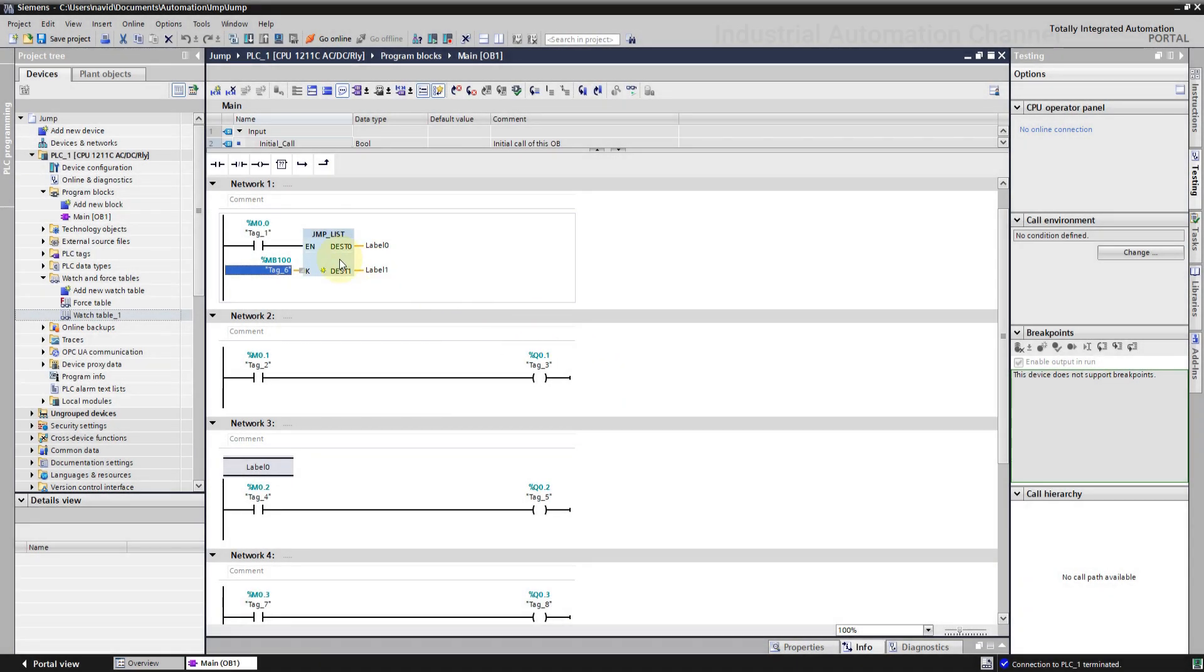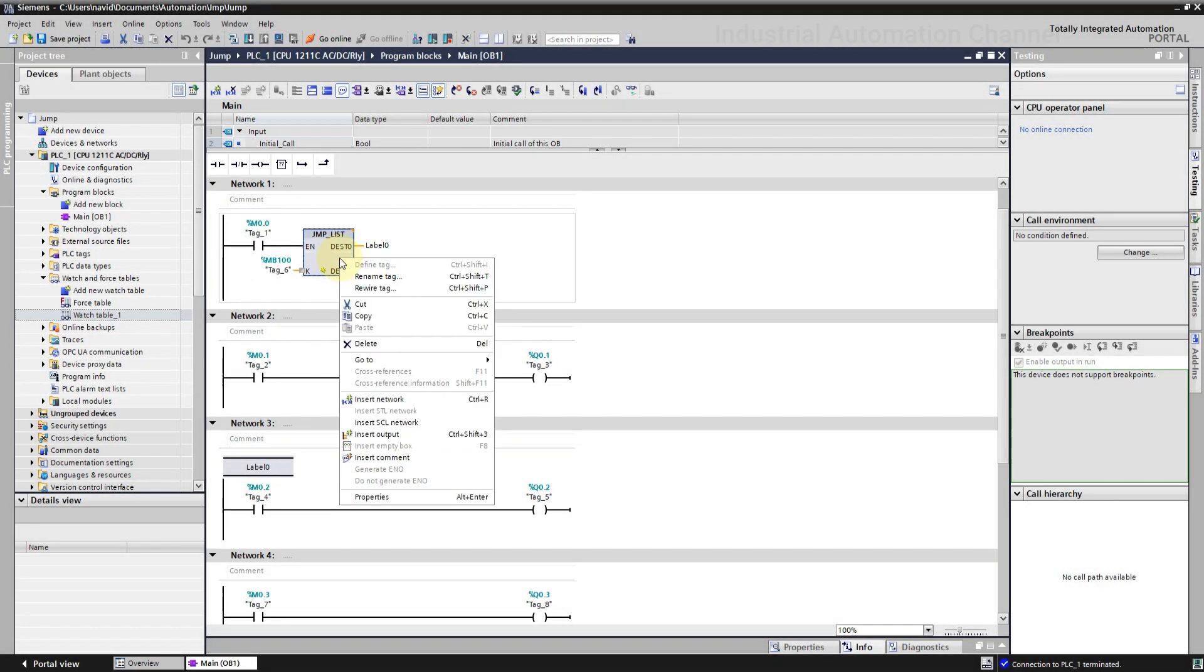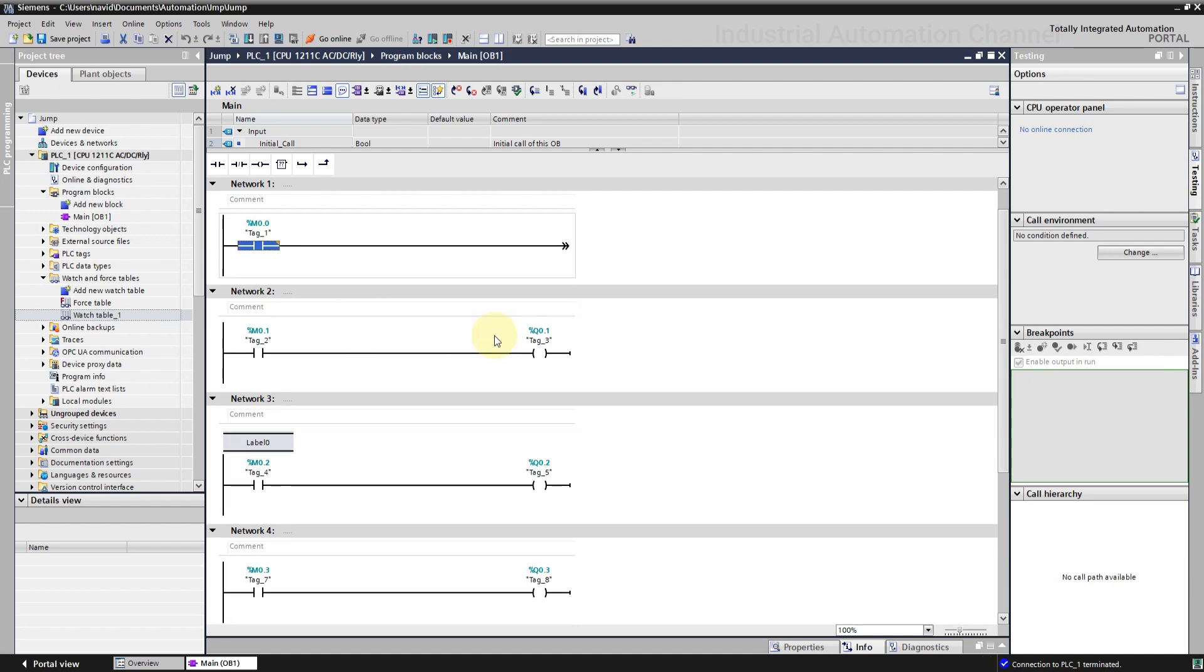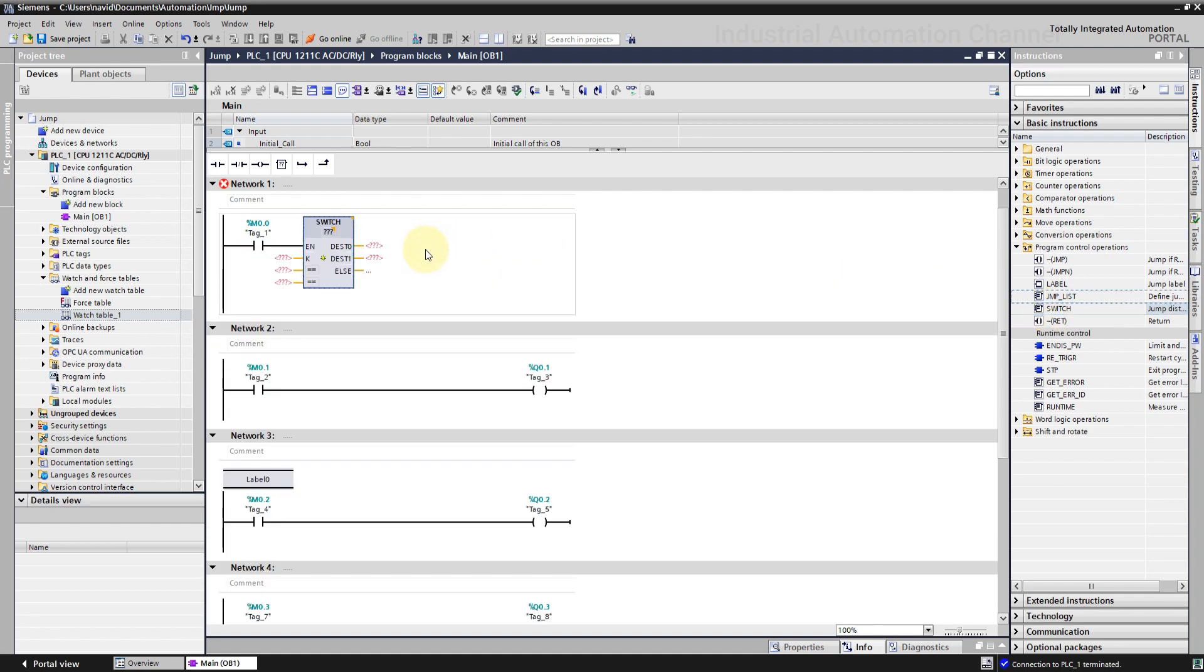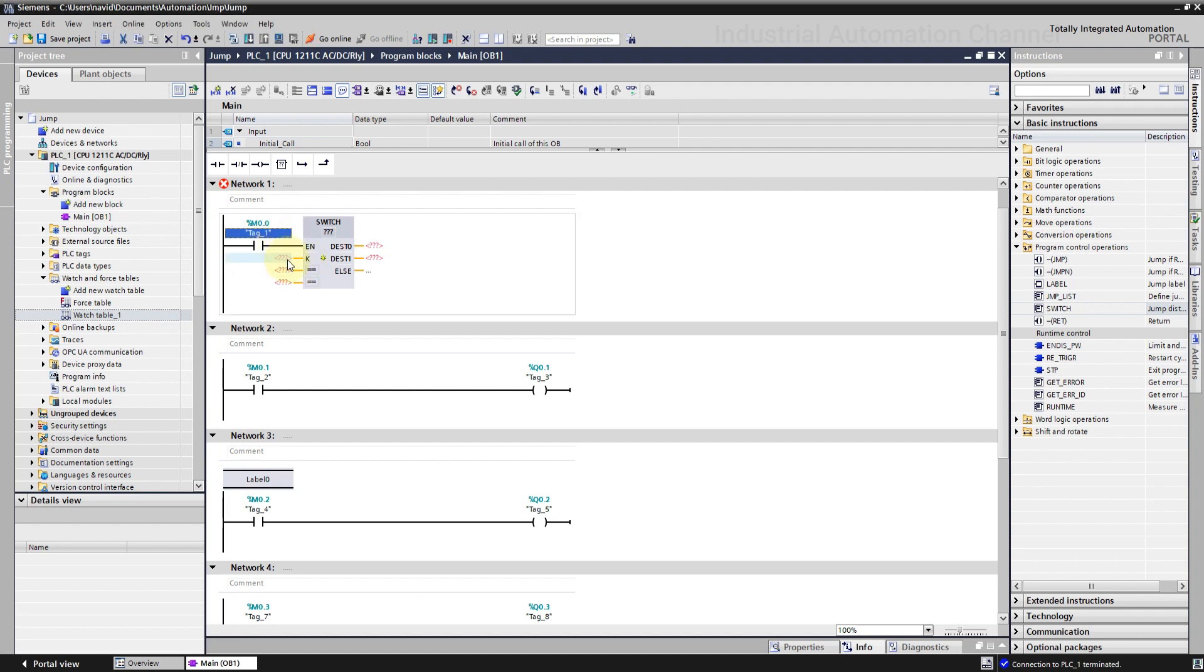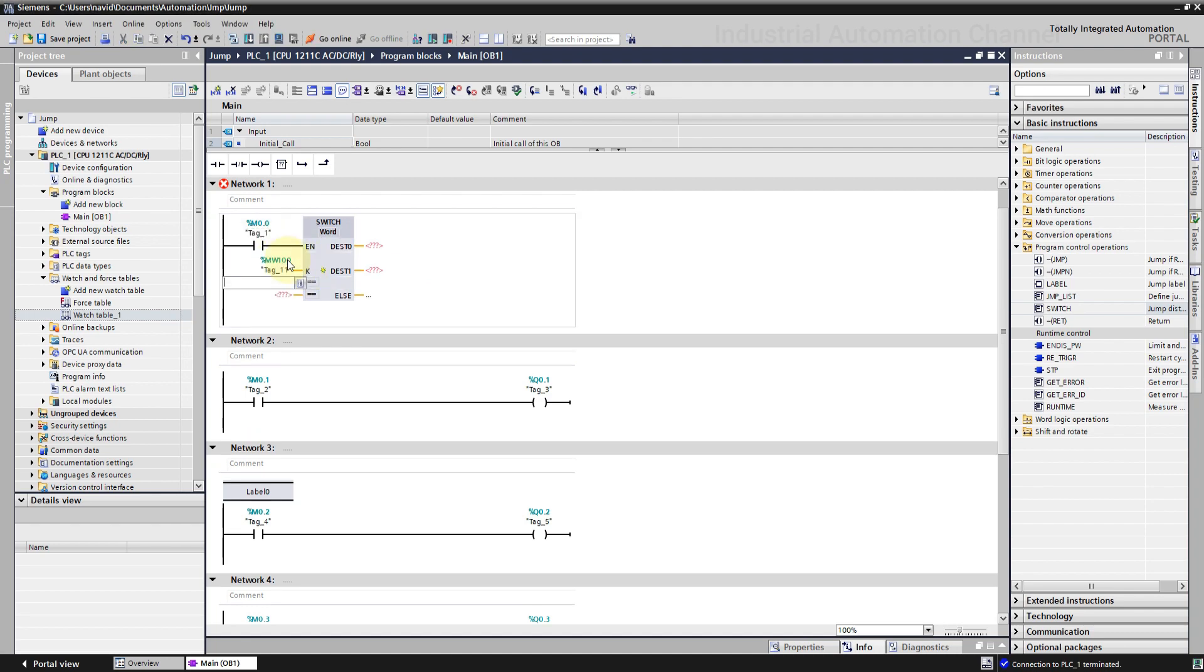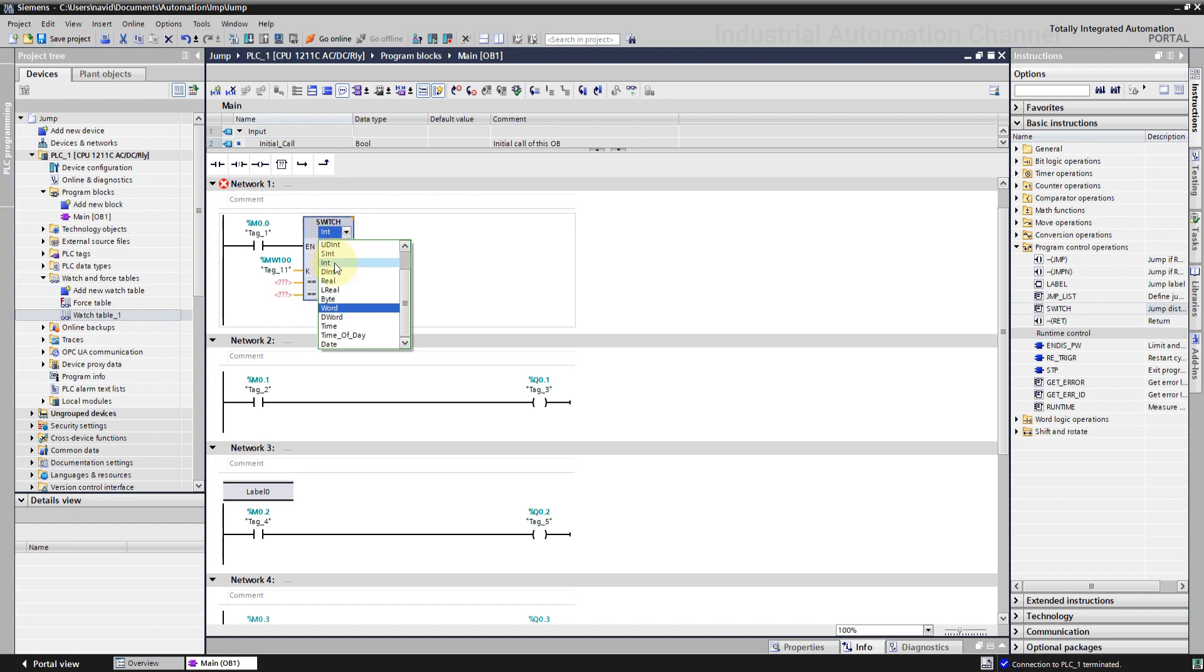Now we have switch. It's similar to a jump list. Here we have also multiple program jumps. But each jump will be done depending on the result of a comparison in the input. So we have here an input to activate the instruction. And an operand to compare and some operators. You can select the comparison method for each individual input.